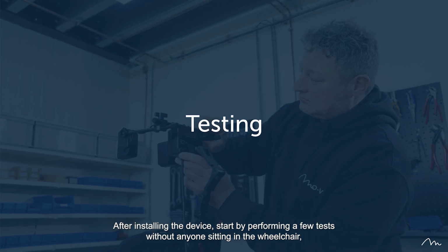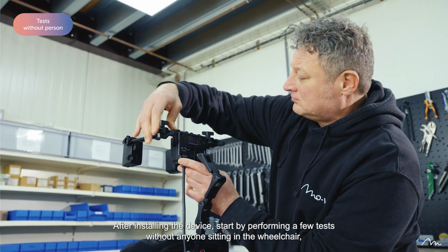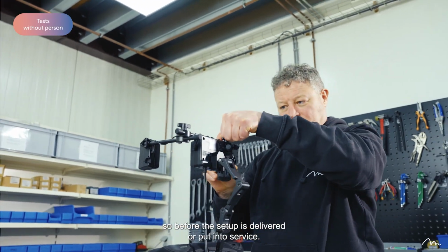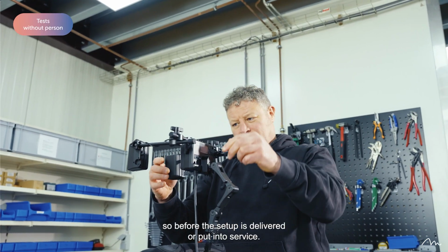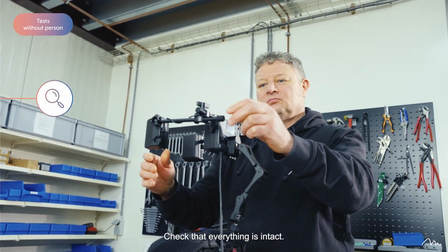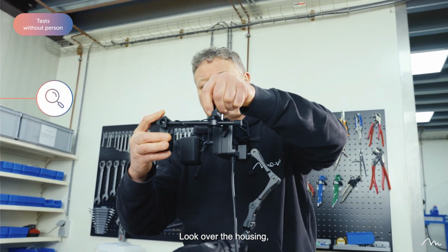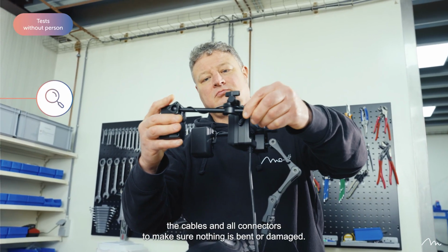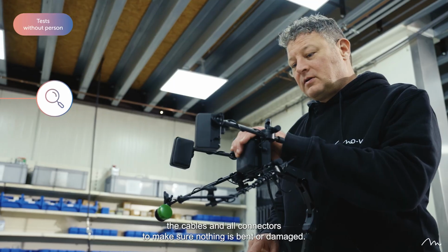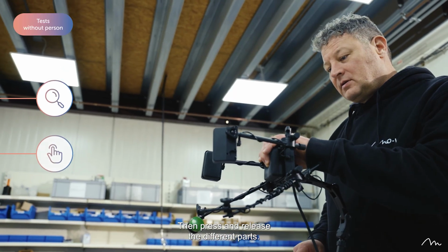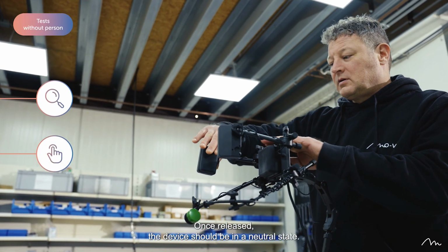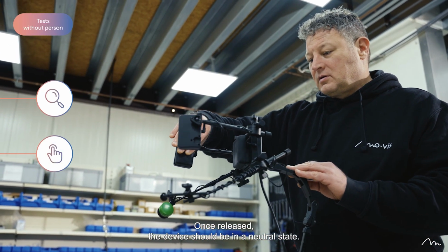After installing the device, start by performing a few tests without anyone sitting in the wheelchair, so before the setup is delivered or put into service. Check that everything is intact. Look over the housing, the cables, and all connectors to make sure nothing is bent or damaged. Then press and release the different parts. Once released, the device should be in a neutral state.